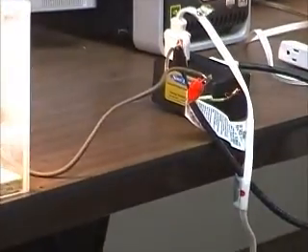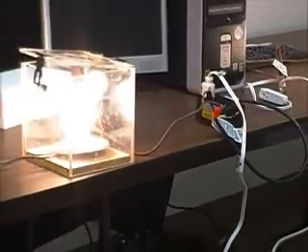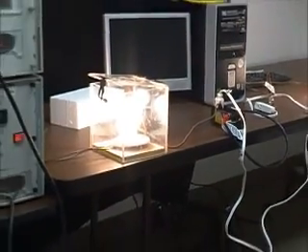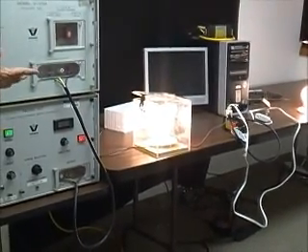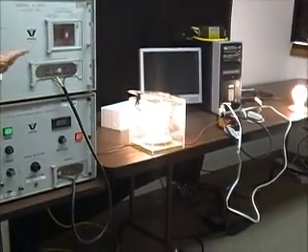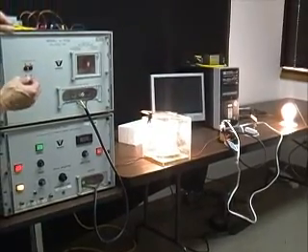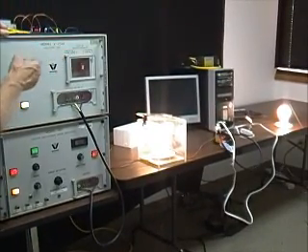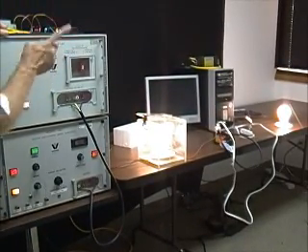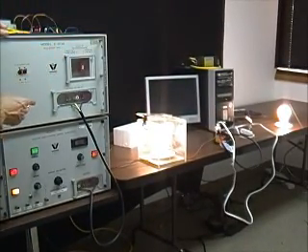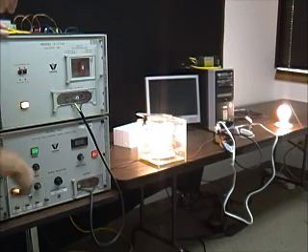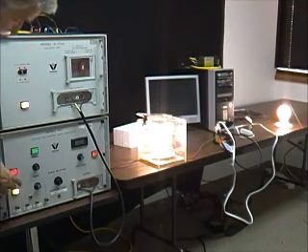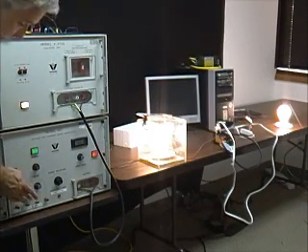So we're going to start with the 100 kilohertz ring wave. And from previous tests, we've seen that between seven, possibly up to eight or nine ring wave impulses will cause the first light to fail. Then we'll look at what happens downstream when we change to the combination wave. Are we ready to test?